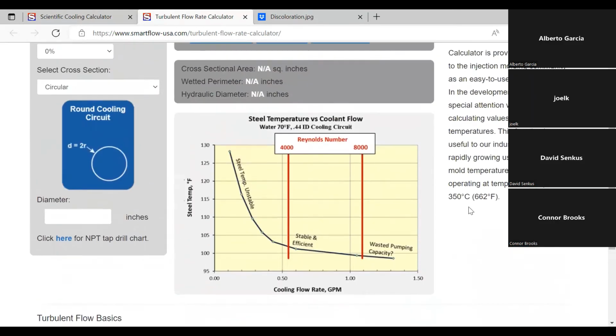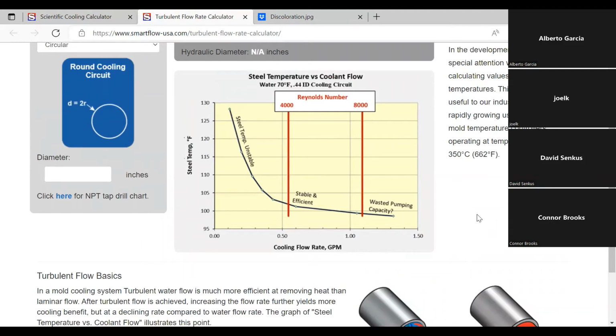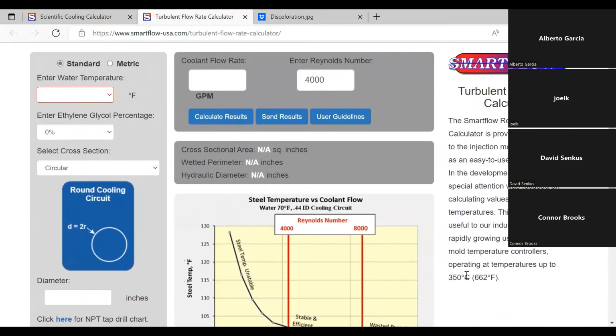If you scroll back up a little, right here is your steel temp on the side. So if your steel temp is 115 degrees and you've got half a GPM, your Reynolds number is below 4,000, whereas ideally you'd probably want to be in the 6,000 range, maybe 5,000. But you can also see that just by increasing the flow, going along that same line at 105, if you find your Reynolds number to be at 4,000, your gains by increasing 0.75 GPM aren't that great at all. You could instead need to increase the temperature of your water - if you scroll up a little, Carolyn, you can see your water temperatures, and if you're adding glycol, the diameter of your tool, then you calculate the results. Then on that previous scientific cooling calculator, you can plug in, hey, I want to hit that 4,000 Reynolds number, and start adjusting your processing parameters.